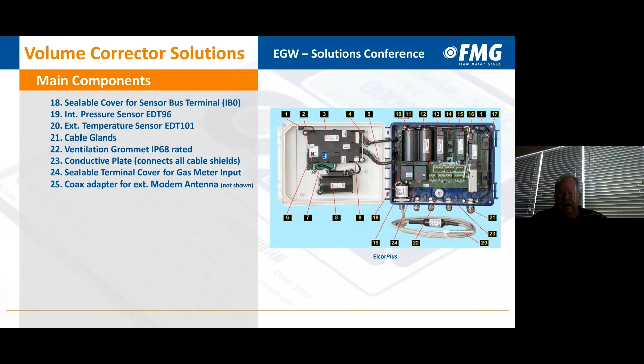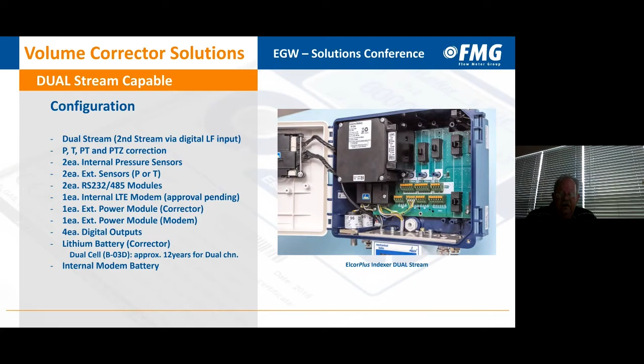Configurations, you can do 1 or 2 meter streams with 1 instrument today, whereas before it was 1 instrument per meter. This particular configuration and manufacturer allows up to 2 for pressure, temperature, pressure and temperature, or pressure, temperature, and super compressibility. As you can see in the lower left of the photograph, there are 2 pressure sensors in this instrument. Likewise, you can put 2 RS-232 modules. You can put 2 temperatures, external power if needed, and 4 digital outputs. The dual battery pack that's installed in here will keep your corrector up and running for about 12 years.